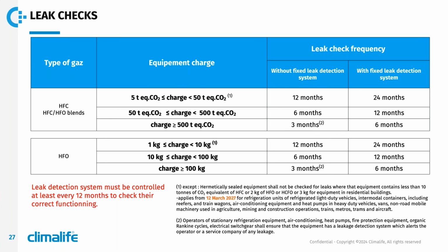The new F-Gas introduced leak testing for HFOs based on the same principle, but the charge is in net kg of refrigerants. So we have a frequency of leak checks according to the net charge in the system. This is as follows: for a charge between 1 and 10 kg, leak control every 12 months, or every 24 months if you have an indirect leak detection system. Between 10 kg and 100 kg, frequencies from 6 months to 12 months with leak detection systems. At 100 kg or more, it is every 3 months or 6 months.